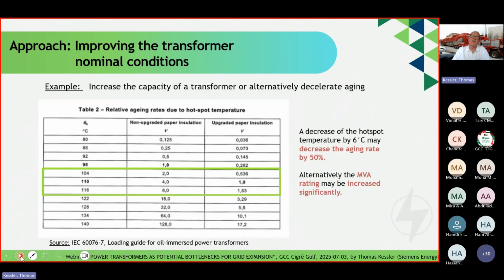Then there is another topic related to transformer conditions. The question is - that was the theory, but what does it mean in practice? What is the physical and chemical starting point to reduce the aging rate of a transformer, or maybe also to increase the transmission capacity? This is well described in the IEC standard 60076, the loading guide for oil immersed power transformers.